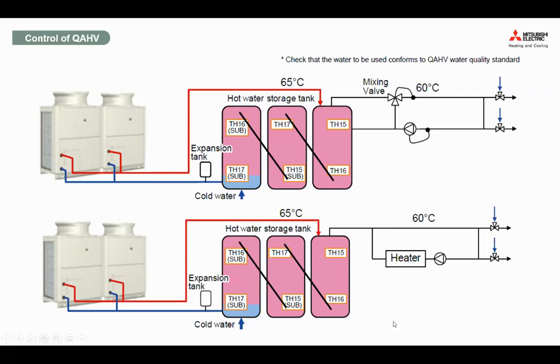And on the bottom of the image, you can see there is a reheater. Just in case your hot water tank is low, and then for the longest time your hot water tank is essentially full. You have a large building, so the 60-degree water traveling all the way throughout your high-rise building, or with poor insulation, may become, let's say, 55 going back in. So you really do need to bring it all the way up to a little bit higher, right?